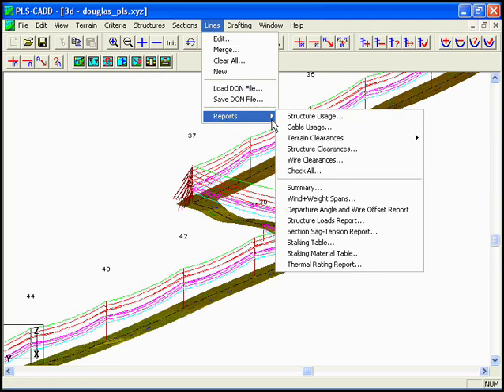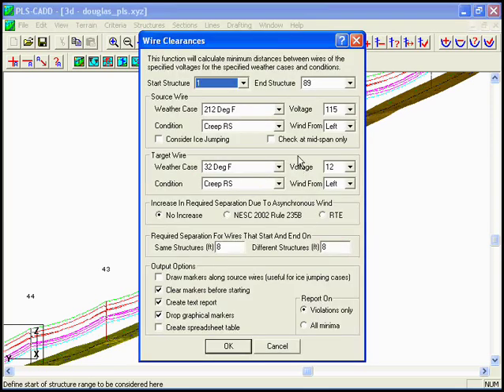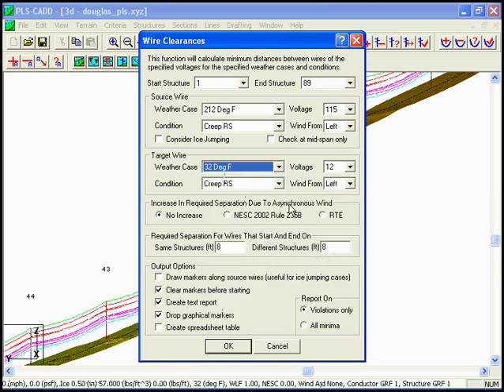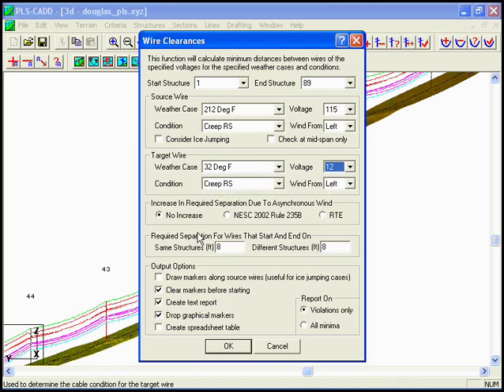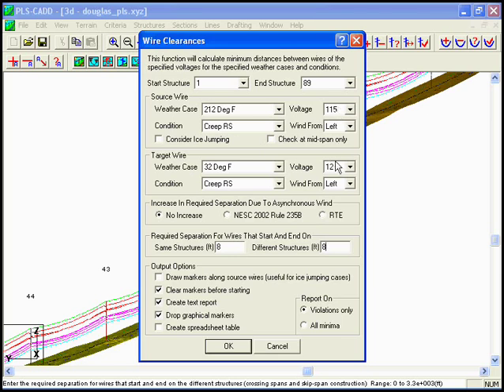So we'll go to reports, wire clearances, and we'll go at 212, 115, and we'll go from our 32 degree F condition on our 12.5 kV circuit. After creep, in the interest of time we'll leave it at 8 feet of clearance between the 115 and the 12 kV, and we'll leave all the reports the same way.